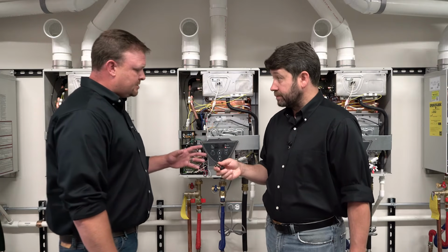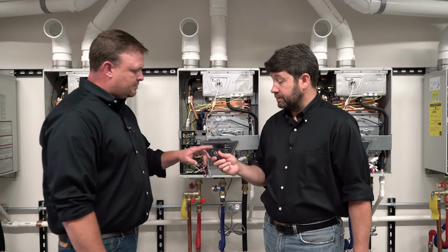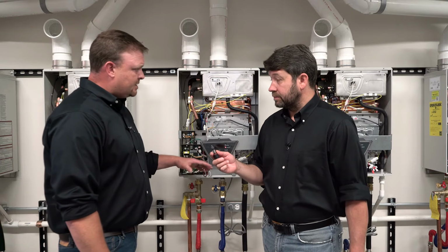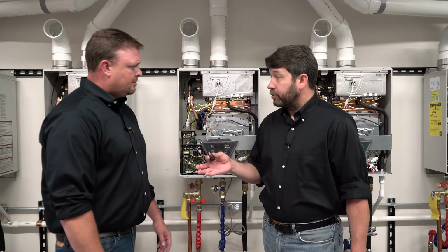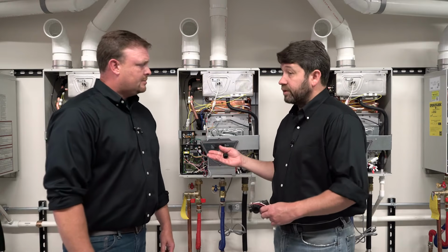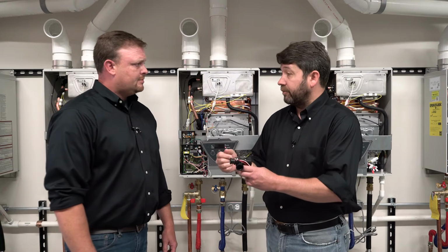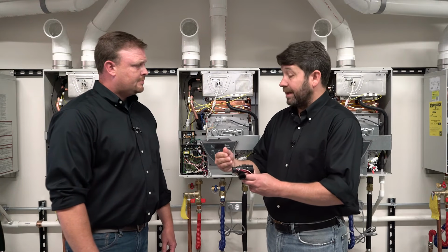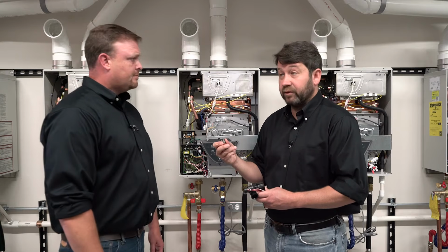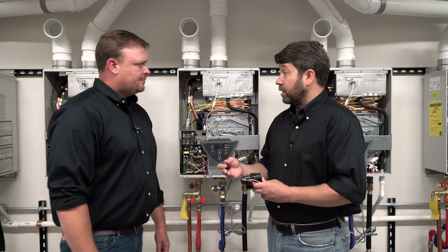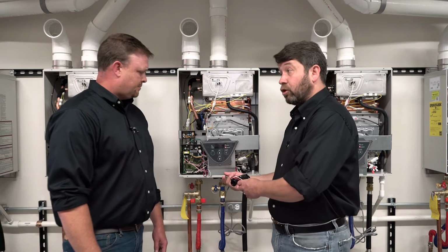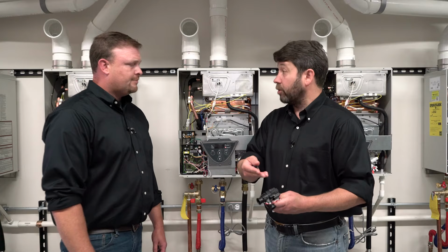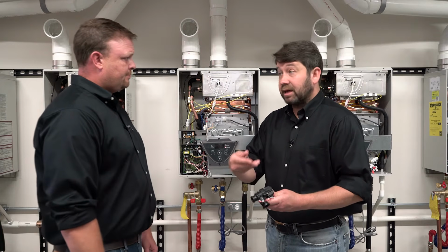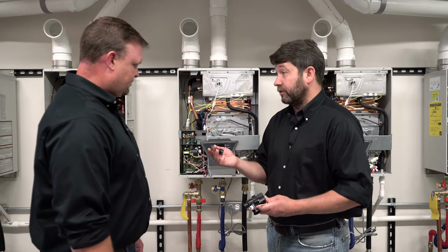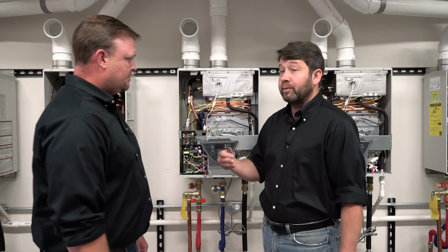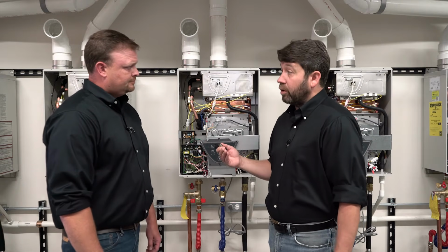Now, on a new installation, is it recommended to check this right after installation, or maybe a day or two after? Maybe a day or two after, and it depends, because when we do a new installation, we've moved the plumbing pipes around, and some of the things that have collected on the inside might break loose and get collected in this filter. Another time is if they're doing any other plumbing repairs in the home, or maybe the water company is doing some repairs out there. That can dislodge some sediment and allow it to collect in here. So this would be the first thing we want to check, because we want to make sure that the water heater can flow water correctly.